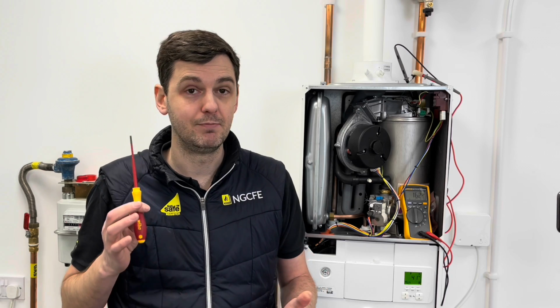You would have to refer to a technical department for these readings, or if you've been on manufacturers' training days, they normally give you that kind of information. But again, it's not manufacturer specific, it can be appliance or boiler specific as well. So get the information you need, and check the readings that you're getting against that. In most cases, if you've got an ionisation fault from the start, it's due to the fact that there's an issue with the burner igniting.